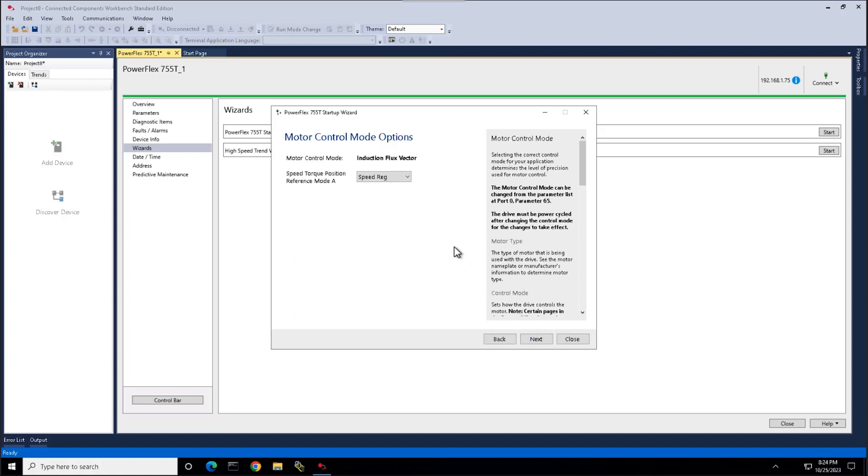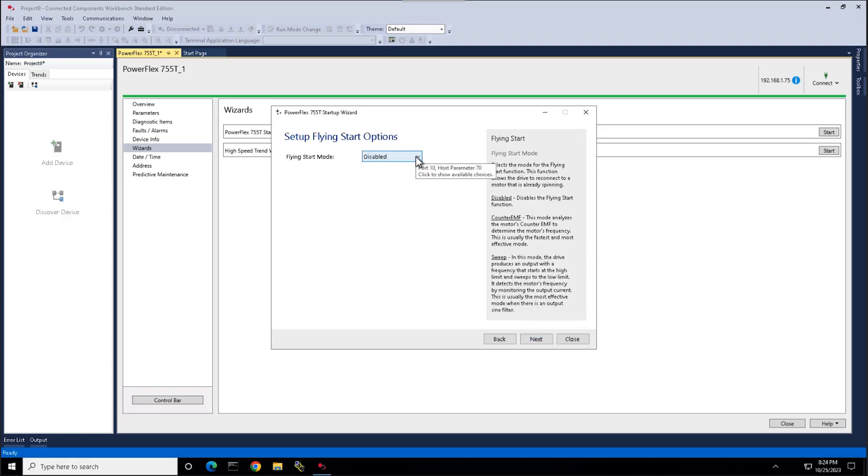Here we have our motor control options. For this example, we're going to use Induction Flux Vector. Here we'll set any flying start options. This allows the drive to connect to a motor that is already spinning.